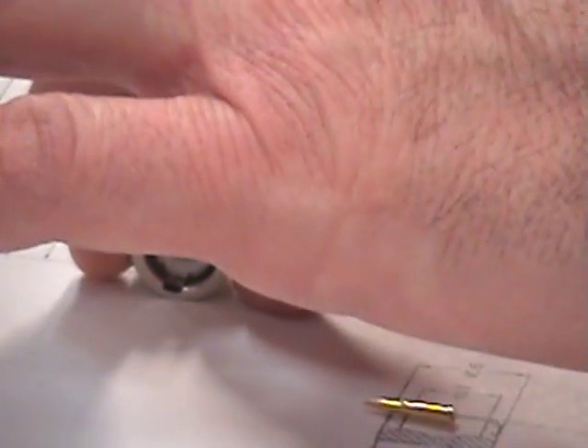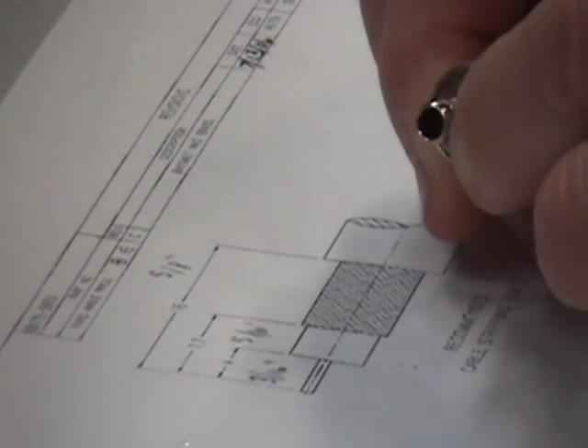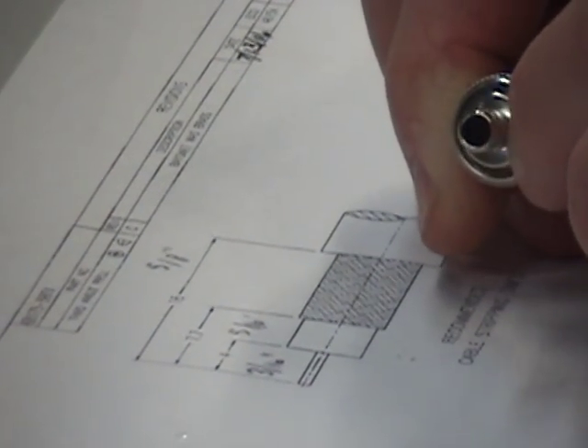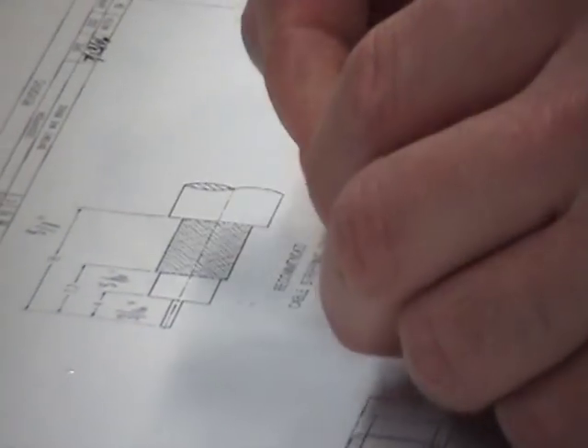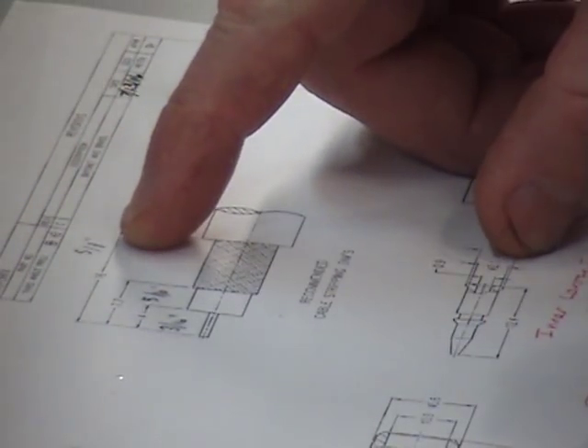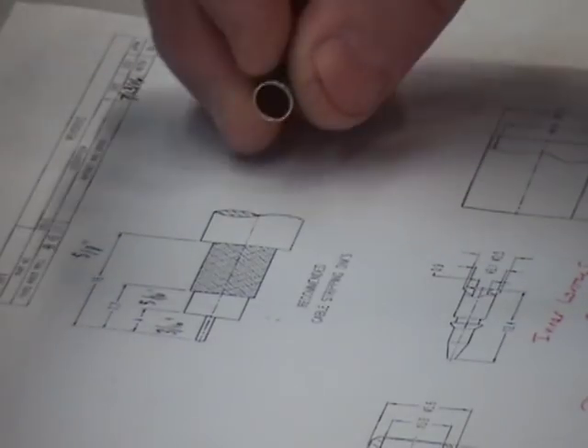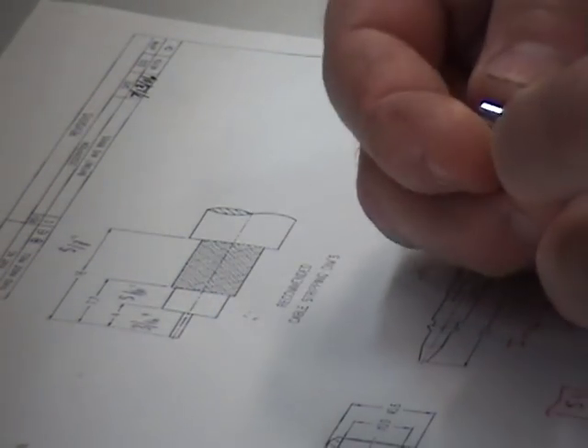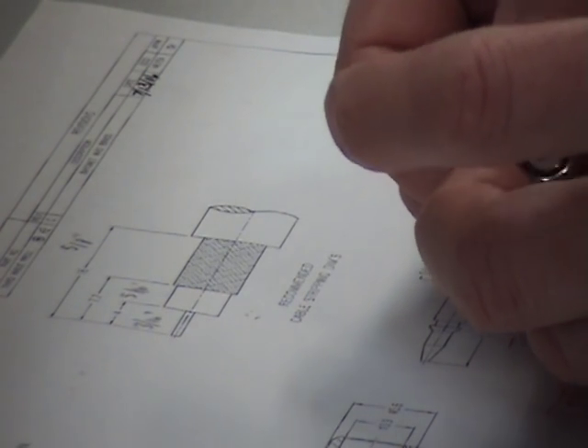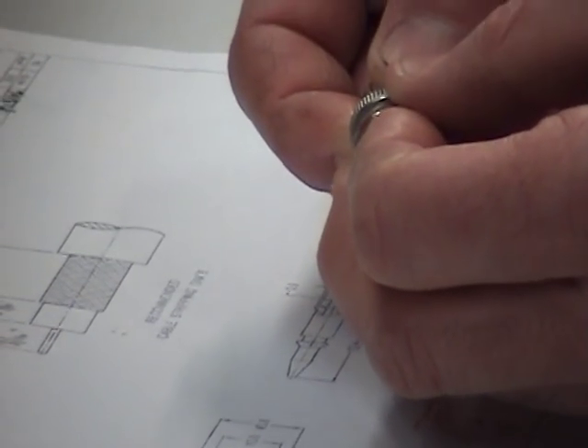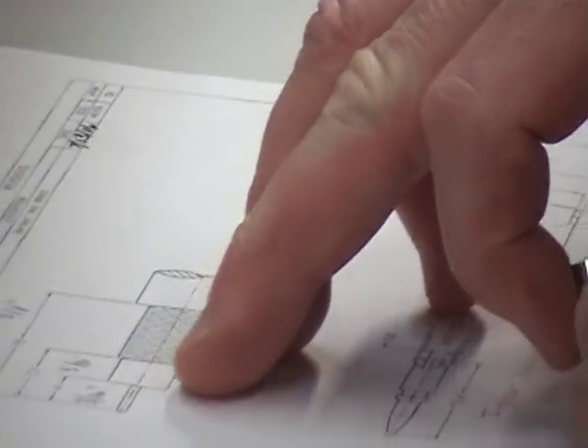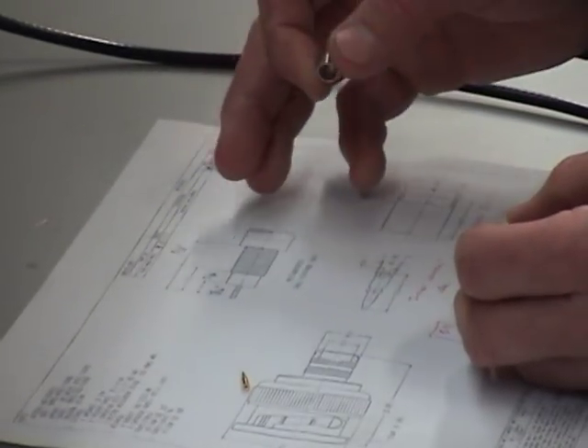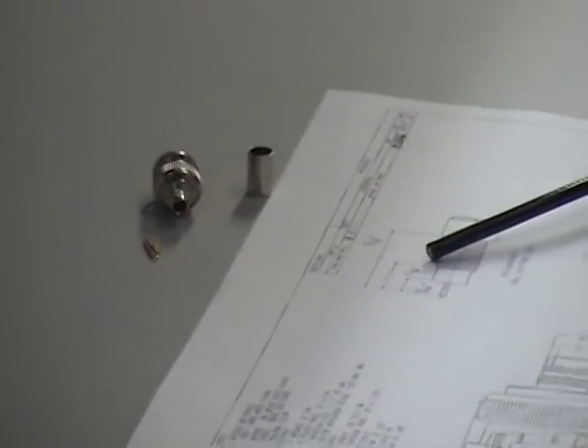The dielectric can only be 5/16ths. Because when I slide in my connector, it's going to slide over the pin, and then the dielectric is going to slide the 5/16ths into the connector, and then the shield is going to go over the top of the 5/8ths strip length. That shield will lay over the top, and then I'll be able to take my outer ferrule, slide it over, and then crimp this onto the ferrule. So you have, with the coax, two separate conductors: the inner conductor and the outer conductor, the shield.